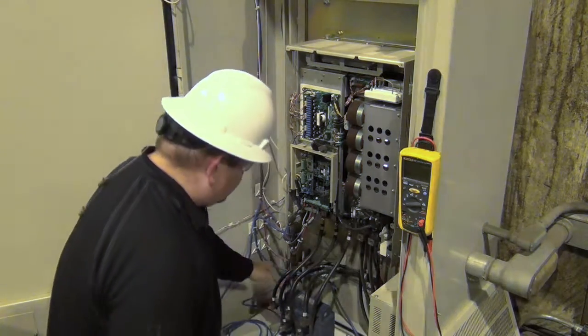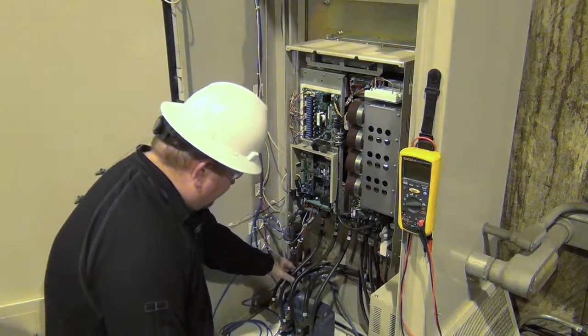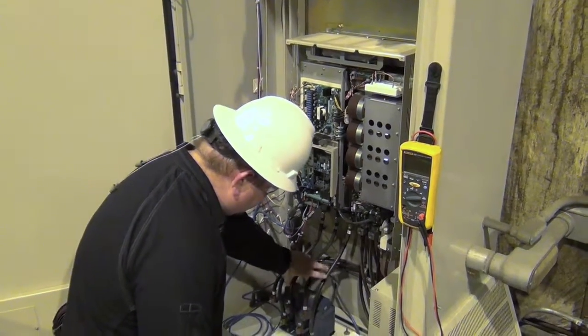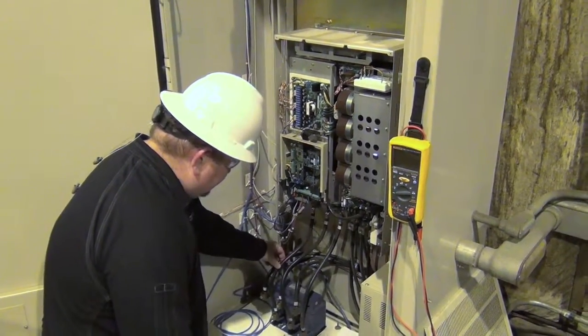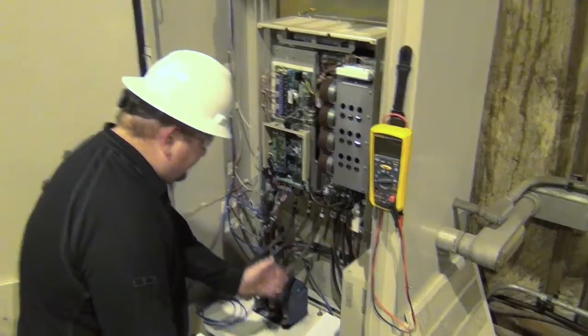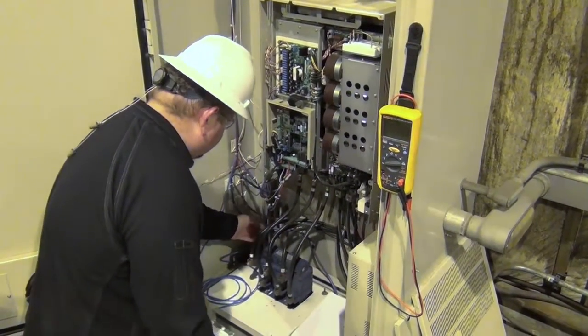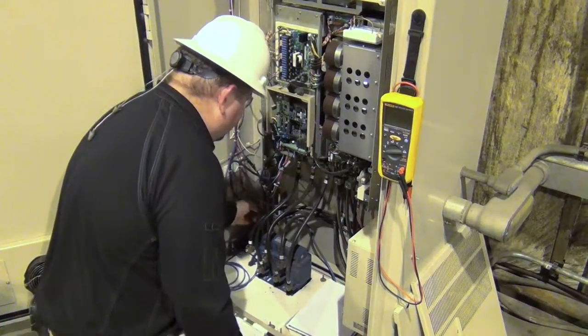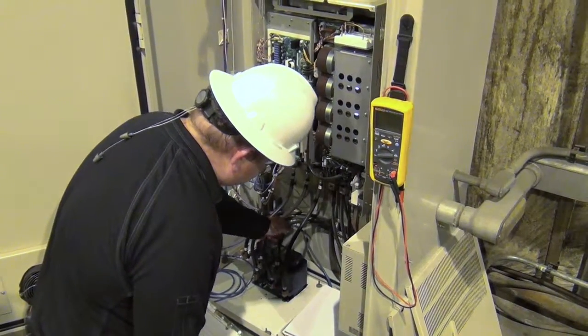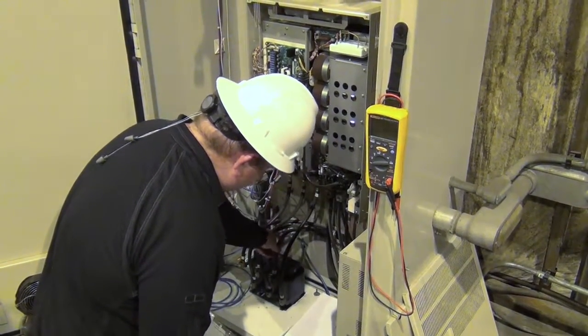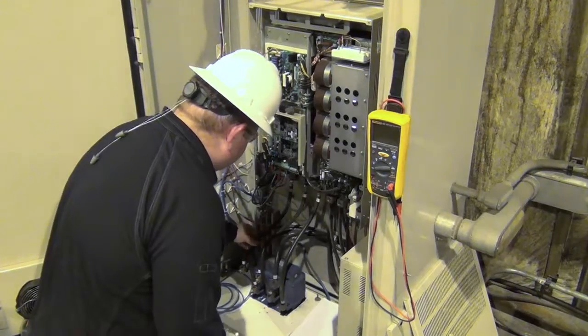So this will bring us to the input line reactor, which is this device down here. This particular one is an MTE brand. So same thing we've been looking for on the drive. We're going to take a look at the coils, make sure we don't see any evidence of arcing, make sure we don't see any evidence of any liquids. Then we're going to verify that all of the connections are snug.